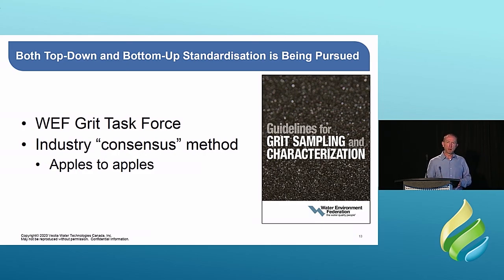Manufacturers have also been part of that. Folks like us who build these systems, provide this technology, also coming together on a way of doing it. In broad terms, how Veolia would recommend that test method is done, our testing standard, and the basis on which our performance statements are now made, is a combination of both the wet sieving with the sand equivalent size analysis and the dry sieving. So it's, you could say, the best of both worlds. It kind of looks at it from different angles and comes at a common number, combines all of that into an average, and that's what we would base our performance statement on. And there's others in the industry doing it that way as well.